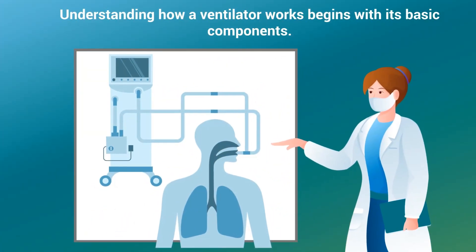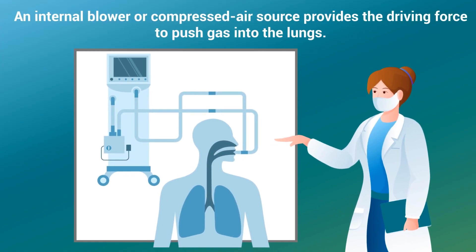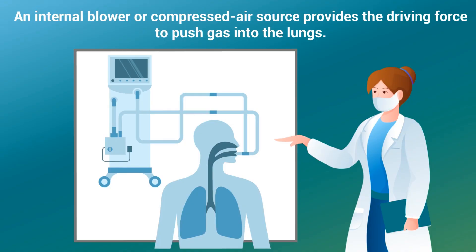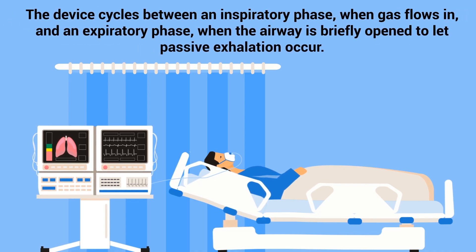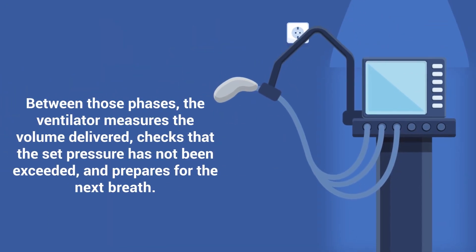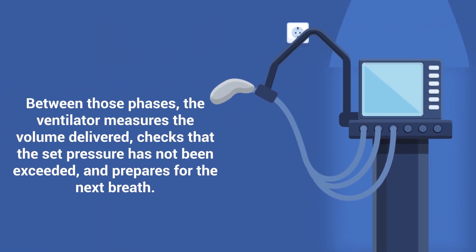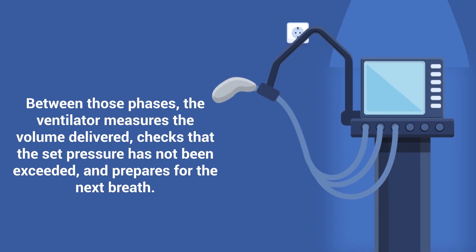Understanding how a ventilator works begins with its basic components. An internal blower or compressed air source provides the driving force to push gas into the lungs. Flow sensors track how quickly that gas moves, pressure sensors guard against excessive force, and microprocessors synchronize all of it according to the mode chosen at the bedside. The device cycles between an inspiratory phase when gas flows in and an expiratory phase when the airway is briefly open to let passive exhalation occur. Between those phases, the ventilator measures the volume delivered, checks that the set pressure has not been exceeded, and prepares for the next breath.